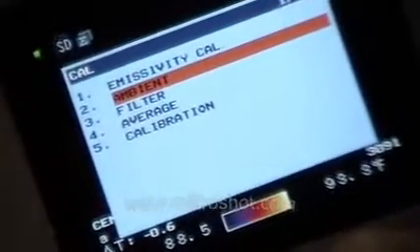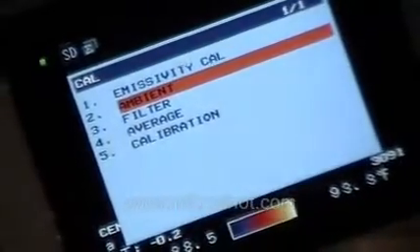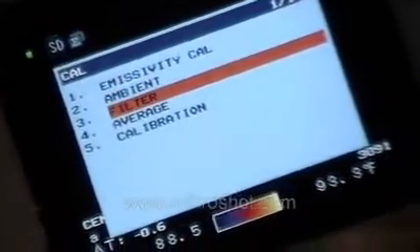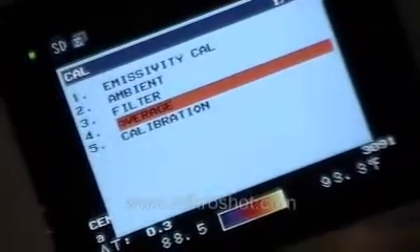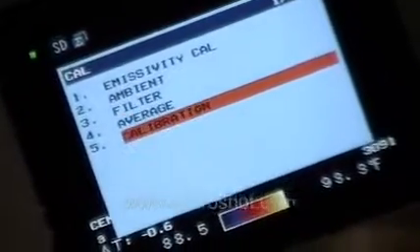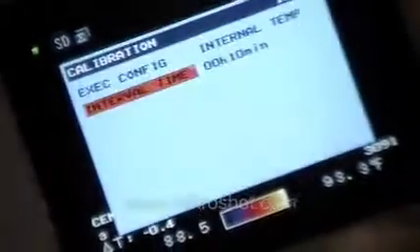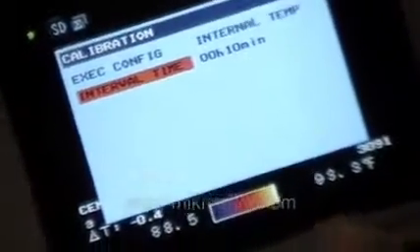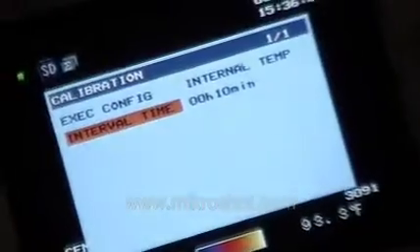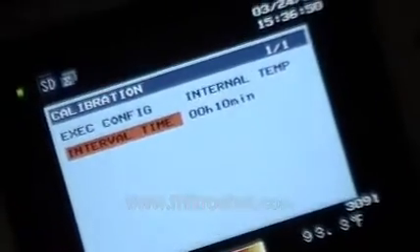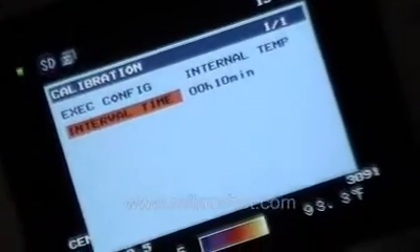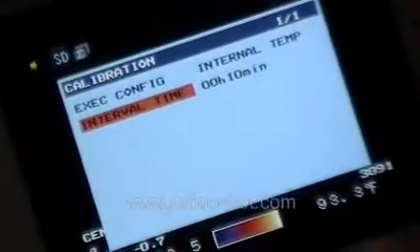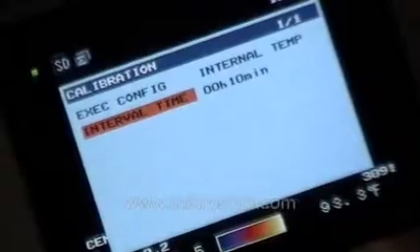We can also set ambient temperature, set filters, averages, and even set the calibration interval for the non-uniformity correction for the uncooled microbolometer detector. The user can set it in terms of hours or minutes.